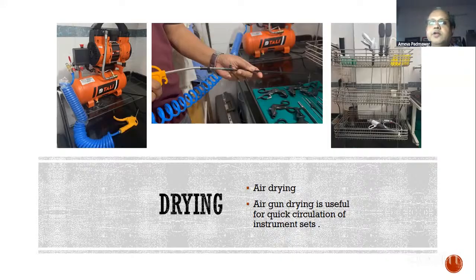On the right side, you have a tray, especially made by one of the vendors which makes kitchen trolleys, you know. So these are steel sieves and trays. In this, we can hang up all our instruments, especially instruments which cannot be taken apart. As I told you, the needle holder, the 5 French instruments, the sonicision probes or the tackers, which you have cleaned, but you cannot dry them. So you have to hang them upside down.